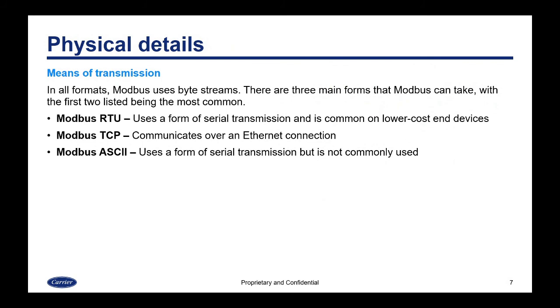In all formats, Modbus uses byte streams. There are three main forms that Modbus can take, with the first two being the most common. The first is Modbus RTU, which uses a form of serial transmission and is common on lower-cost end devices. The second is Modbus TCP, which communicates over an ethernet connection. There is also Modbus ASCII, which uses a form of serial transmission but is not commonly used.